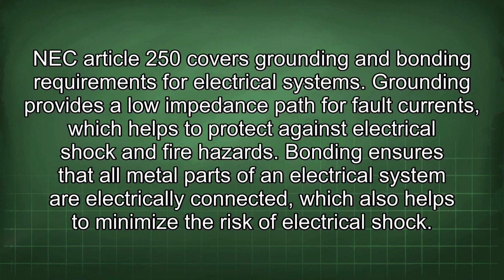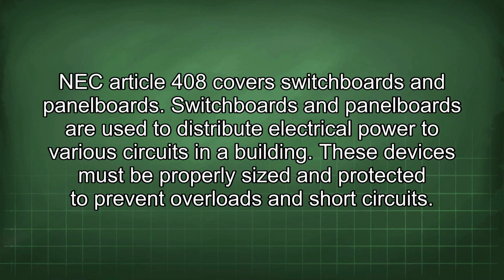NEC Article 250 covers grounding and bonding requirements for electrical systems. Grounding provides a low impedance path for fault currents, which helps to protect against electrical shock and fire hazards. Bonding ensures that all metal parts of an electrical system are electrically connected, which also helps to minimize the risk of electrical shock. NEC Article 408 covers switchboards and panel boards.